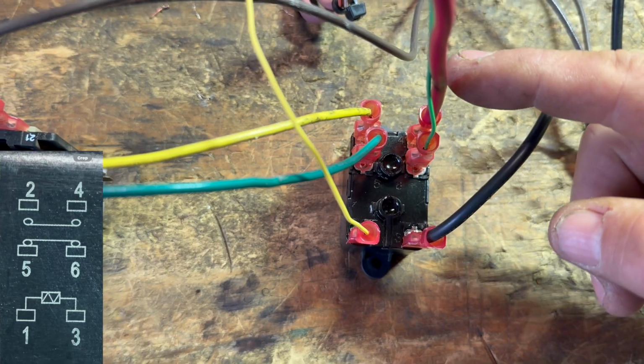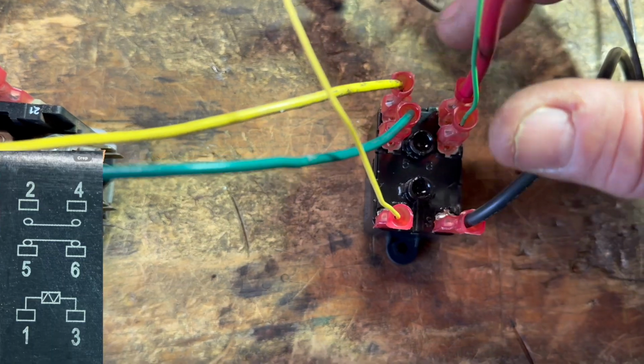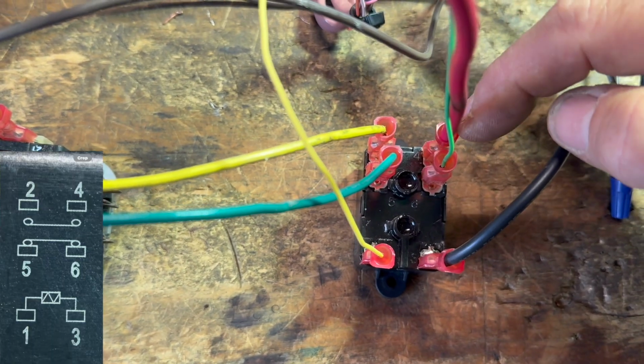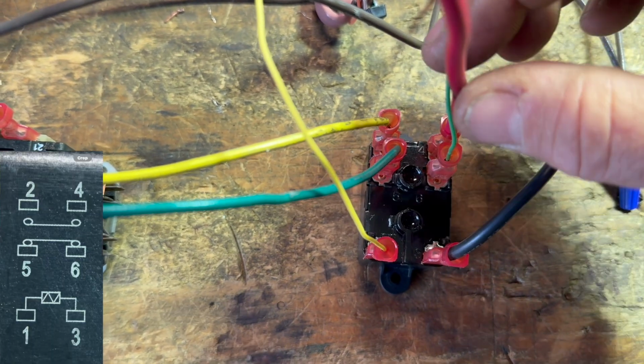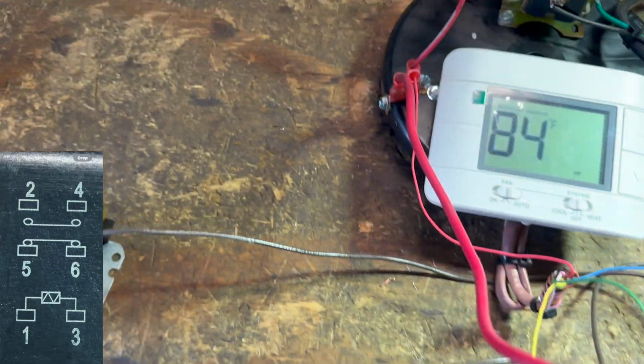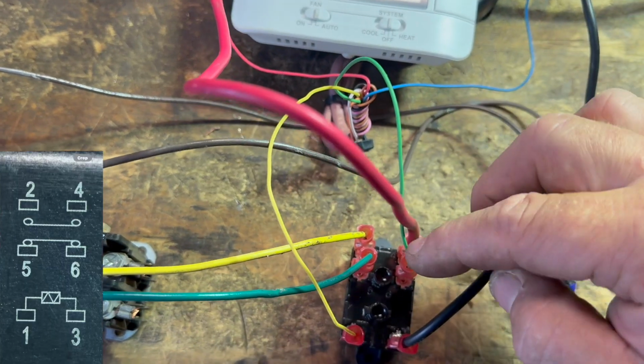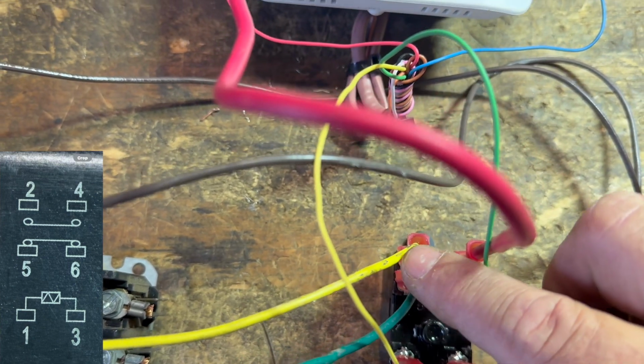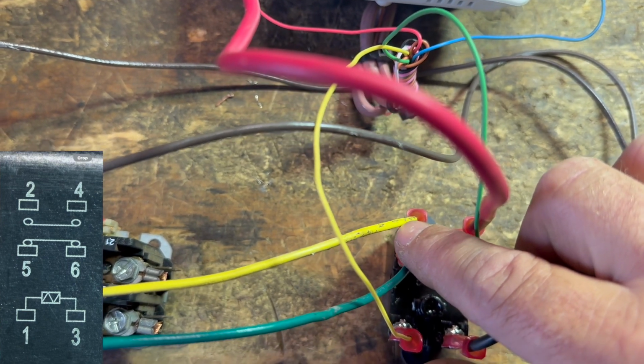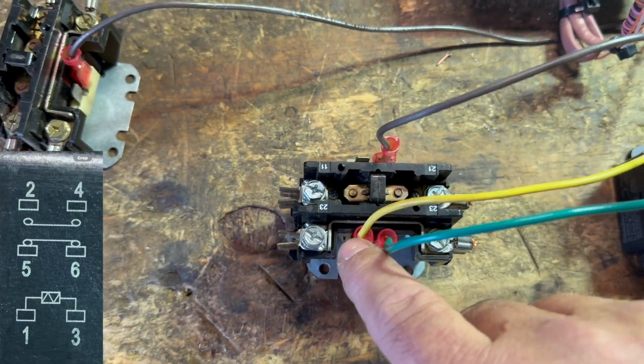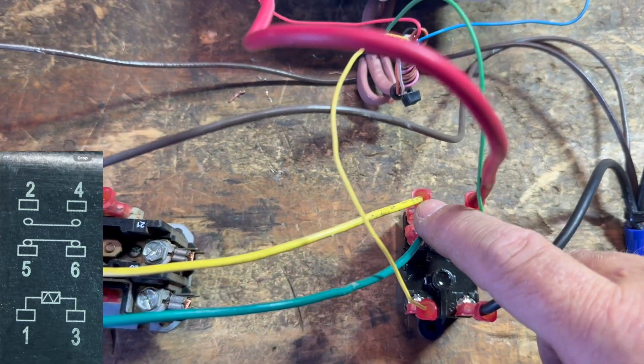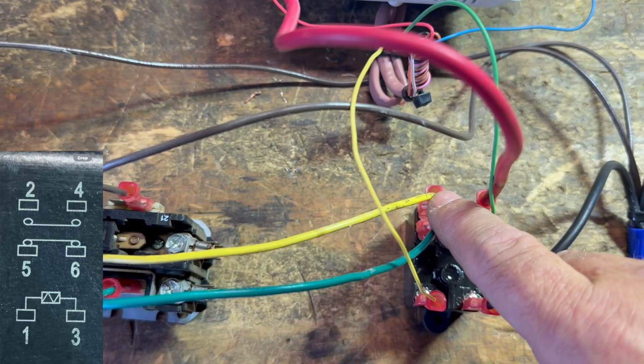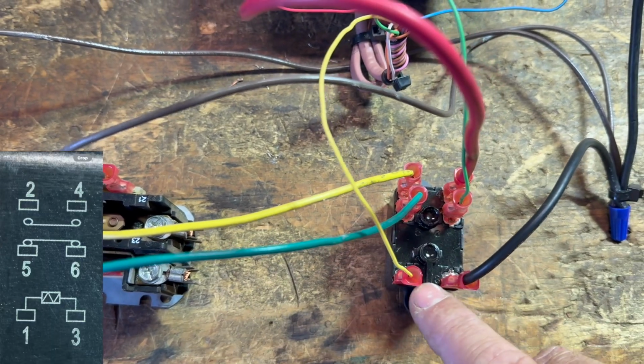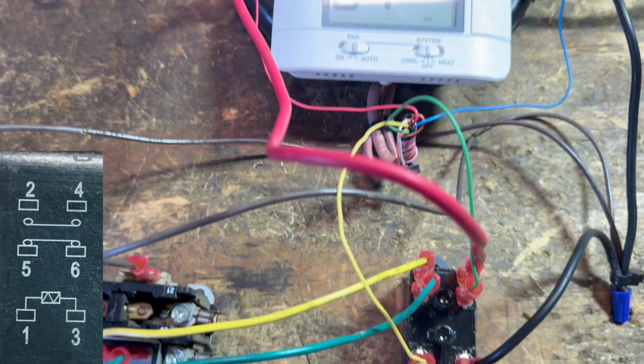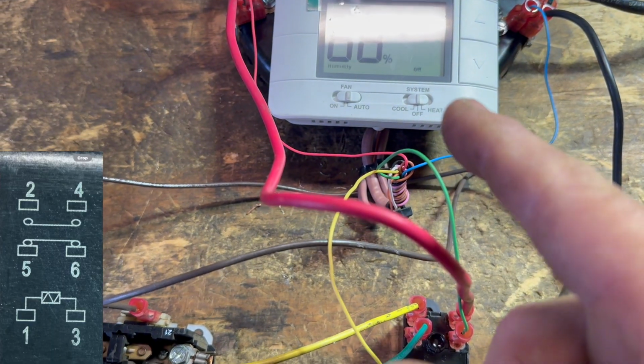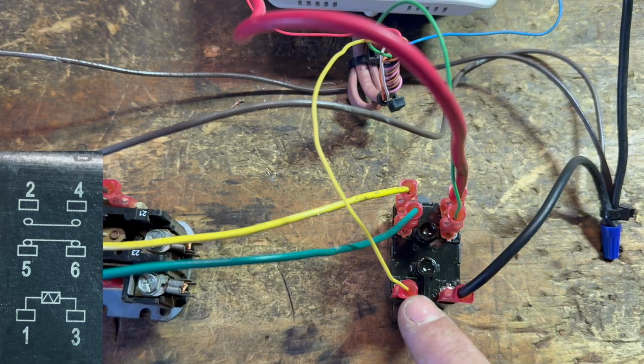Okay. Up here, between numbers 2 and 4, you have a normally open circuit. So what I have is a positive 24 volts, this big red wire, going straight in. And then we're going to say that this yellow is our cooling. And we want it to turn on the fan as well as the outdoor unit. So what I'll have here is this yellow will actually turn on the fan, and it will take the input from this yellow, which goes to the thermostat. So the thermostat will send 24 volts through here.